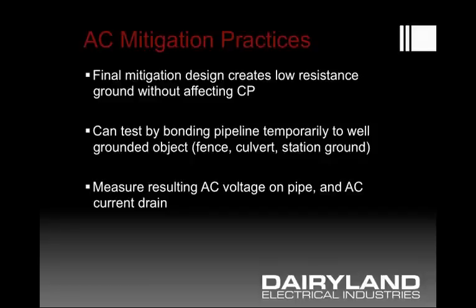The AC mitigation grounding system would be the system that is a low resistance ground. Ideally, you'd have that installed where it does not affect CP — that's where the decoupler comes in. One can test to determine what these effects will be: if one was to bond temporarily and safely to an existing grounded object — it could be a culvert, a road casing, or a fence — something representing a low resistance ground, you would see the induced AC get collapsed to some degree. You can also measure the resulting voltage and use a clamp-on AC ammeter to determine what AC current is available through the coupled source.